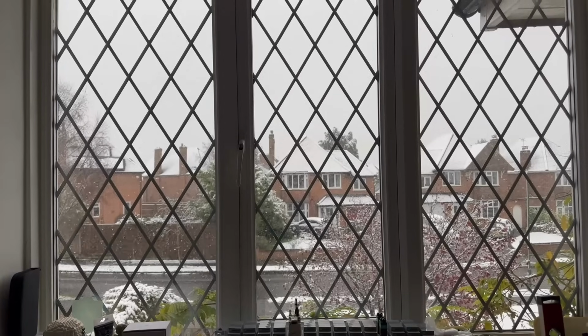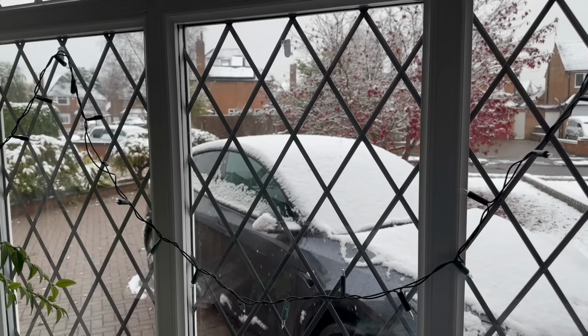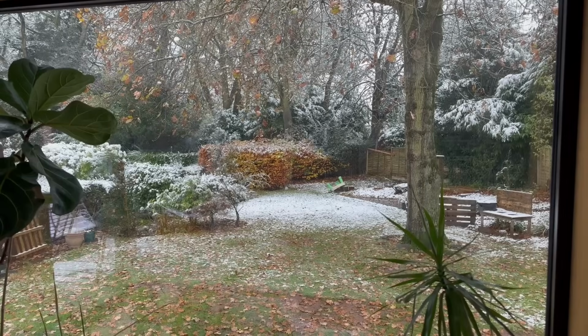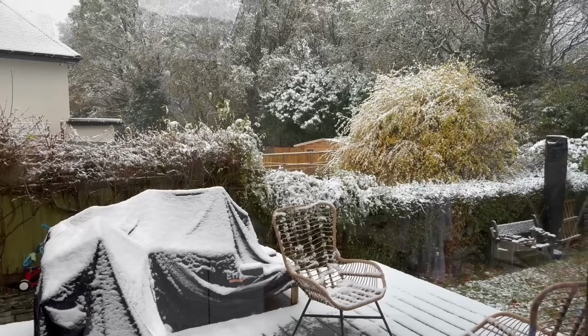All I needed was a period where the outdoor temperature would be pretty consistent. Thankfully, the UK weather obliged. With snow on the ground in mid-November and a cold snap forecast for a couple of days, the conditions were perfect to conduct my test. I would use my normal flow temperature for a couple of days at the beginning of the cold snap before switching to the higher flow temperature for the last couple of days of the cold snap.